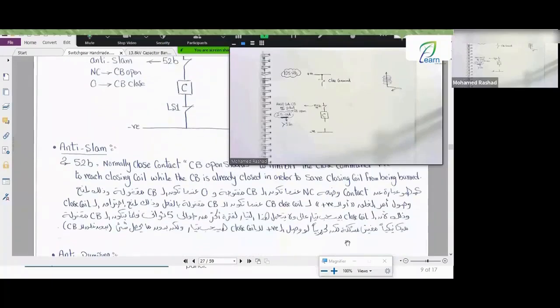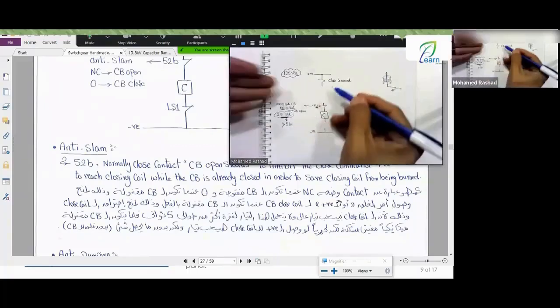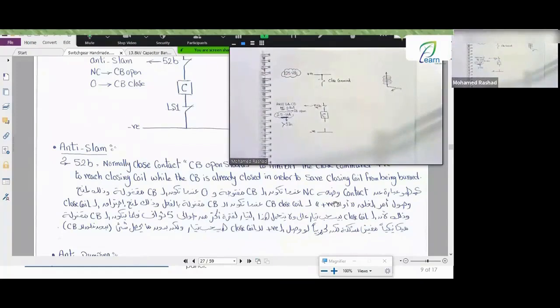All right, you will find that I have explained this part here. Here I have explained the anti-slam, which is a contact that is normally closed when the circuit breaker is open and open when the circuit breaker is closed. This is to prevent the closing command, which is the positive, from reaching the closing coil when the circuit breaker is already closed. The closing coil draws a high current, as I mentioned to you, and it cannot withstand this current for more than 5 seconds.